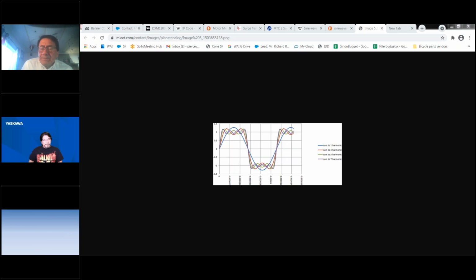So with all that said, we think we understand the issue. And we now are seeing that the manufacturers are, in their terminology, making a recommendation, Craig. I'm not seeing anybody overtly coming out and saying, if you do not use a sine wave filter, we will not honor the warranty. Have you seen that? Yes, I've seen that. Grundfos has actually got that verbiage in their literature. Most of the vertical hollow shaft guys have it in their literature, but what we find is that the field reps are kind of easing everybody into it, because when you put a sine wave filter on the back end of a drive, you're basically doubling the cost of the installation.